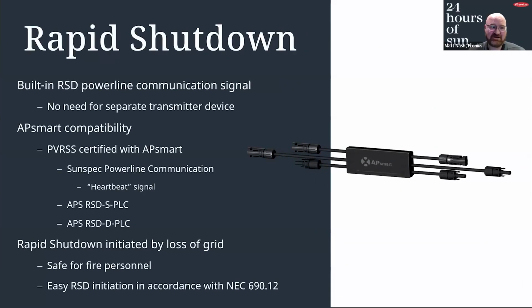And speaking of rapid shutdown, the inverter has built-in power line communication for rapid shutdown devices. There's no need to purchase a separate transmitter device. And for PV RSS, we are certified with APsmart. This is the RSD single and the RSD dual. And as most of you are aware, rapid shutdown is a requirement almost everywhere in the United States, and it's for safety for fire personnel.